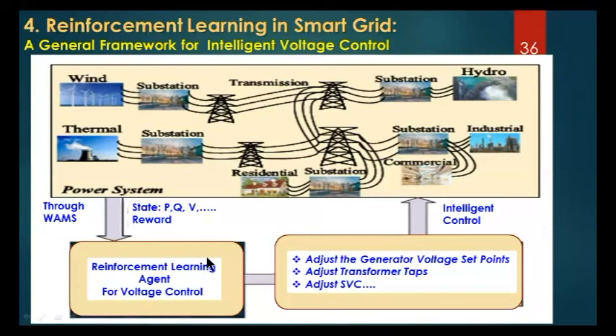Based on its input, the agent follows certain policies, like adjusting generator voltage set points, adjusting transformer taps, adjusting static VAR compensators, and so on. Based on the state and reward input, the agent performs intelligent control, which may improve the voltage profile in the system. If it improves, the agent gets a reward; otherwise, it gets a penalty. Just as discussed before, it learns the voltage control by itself automatically, and once the strategy is identified, the voltage control is done by the agent at ease and becomes automatic.